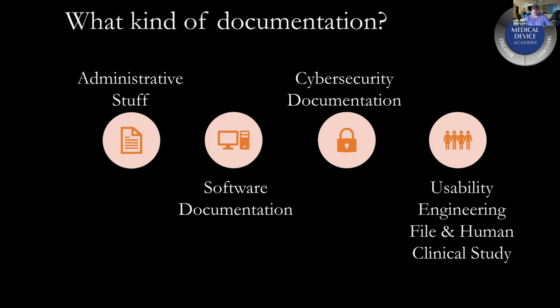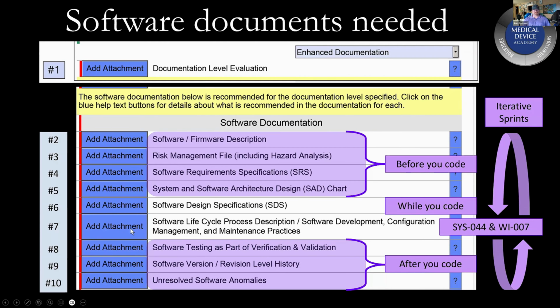I don't even have to claim compliance with 62304. The FDA actually has a place for this, in the software documentation section. It's either the fifth or sixth requirement for an attachment, and I can show you where that is. There we go. Here's a screen capture of it. Attachment number 7: you have two choices. You either attach a certification statement saying you comply with 62304, or you attach all your procedures explaining how you meet all the requirements that are in 62304.